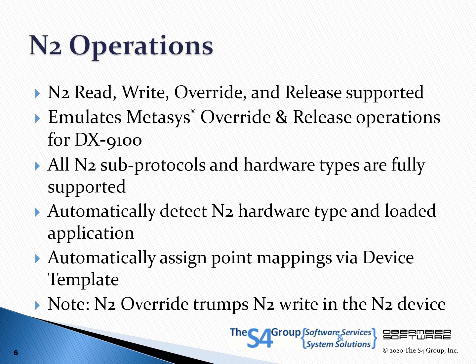If activity on the N2 bus stops for a period of time, approximately 10 minutes, most N2 devices will release all overrides and go into a local operation mode. This is normal operation for N2 devices and cannot be changed.